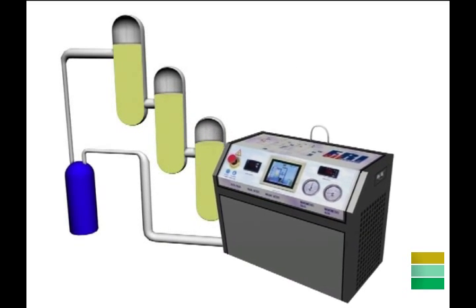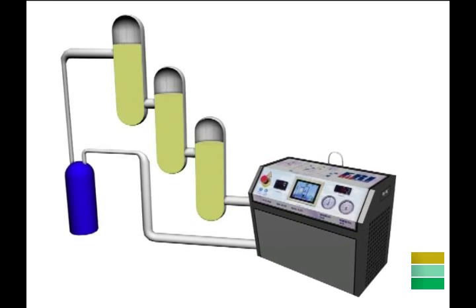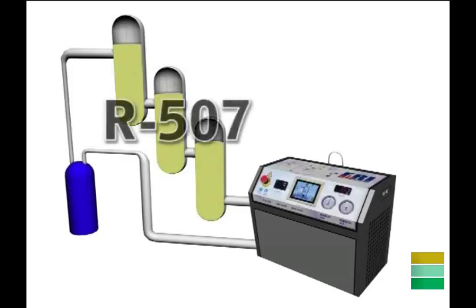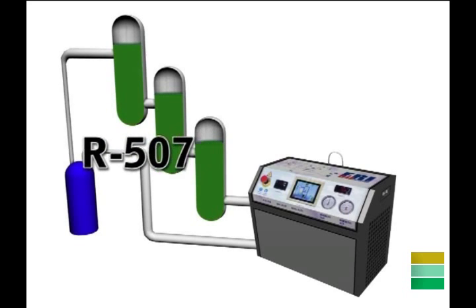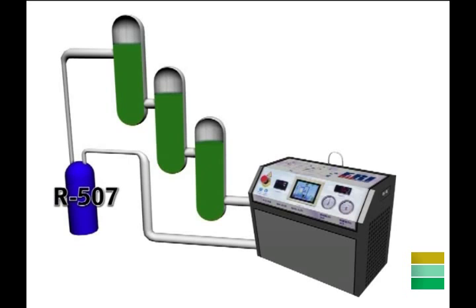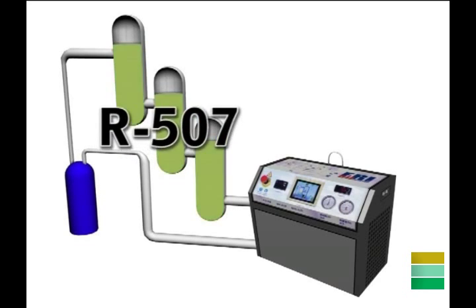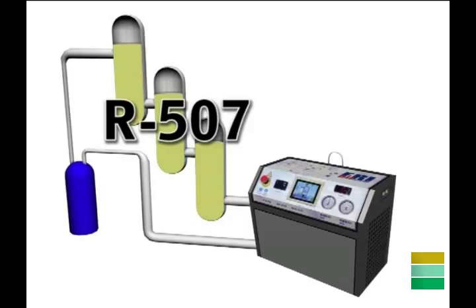Let us consider this example: imagine that we have to clean an installation with 300 kilos of HFC R507. If we use the same refrigerant for cleaning, at the end of this process we will be able to recover the coolant to allow the operation of the equipment. Of course, it will have been necessary to replace the dryers.